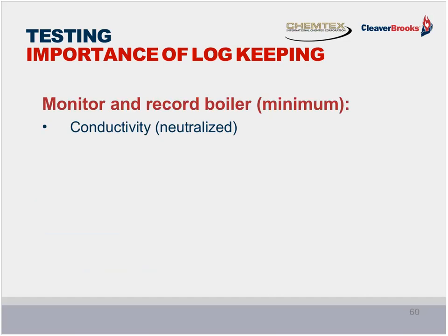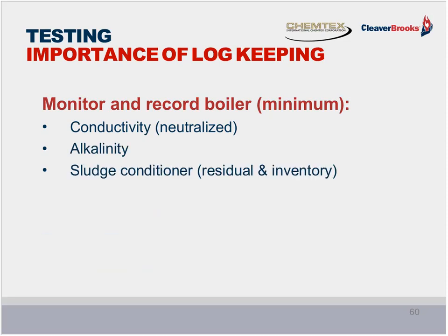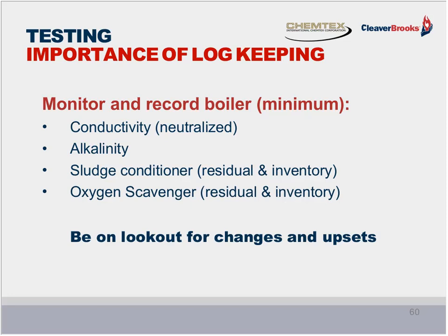In the boiler, you want to monitor neutralized conductivity, alkalinity, and sludge conditioner, as well as oxygen scavenger. At a minimum, you want to be maintaining that. And I recommend that you monitor the inventory of the sludge conditioner and oxygen scavenger to make sure that they're really going into the system and there isn't some interference being caused by some of the more sophisticated testing that's done in the system. Another thing is that you want to make certain that you're on the lookout for changes and upsets.